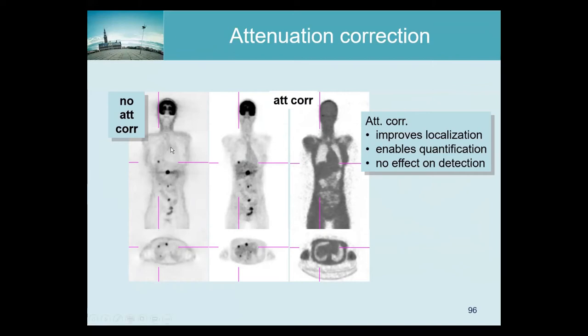The advantage is that we measure the attenuation at exactly 511 keV, which is exactly what we need. If you don't correct a non-TOF PET image for attenuation, you get a horrible image. For example, the lung appears slightly more active than surrounding tissues, while in reality it's the other way around. The liver appears almost uniform, while in reality there is a liver lesion making it non-uniform — cold in the center and hotter at the outside. The skin always looks very active, which is not true at all. This image is by no means quantitative.